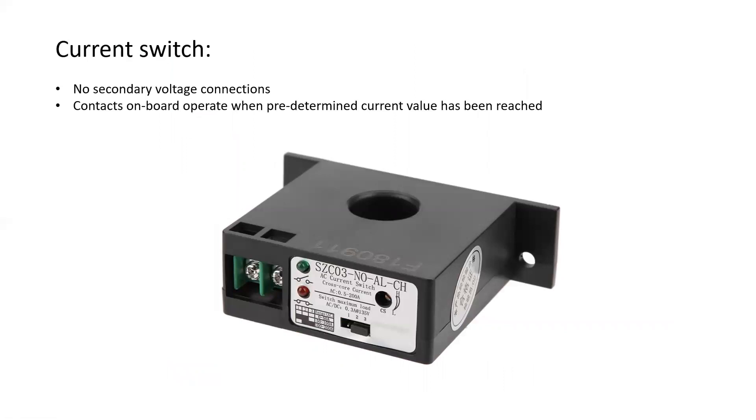One of the other ways we can use it is with what's called a current switch. Now there's no secondary voltage connections on a current switch. And what instead it has is a couple of terminals for a normally open or a normally closed contact. So what it has inside it, it's got a little relay. And it's using the secondary voltage of that coil to operate the relay. So when the current reaches a predetermined value, which is set by that little screw there, it will close the set of contacts and we can use it to then operate any other type of predetermined control sequence that we need. Current switches are used a lot in HVAC controls.